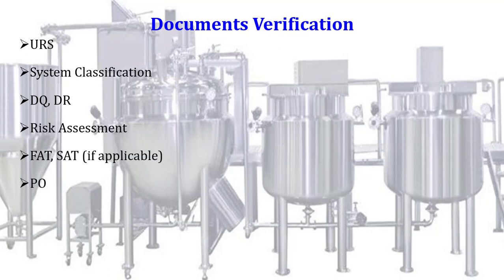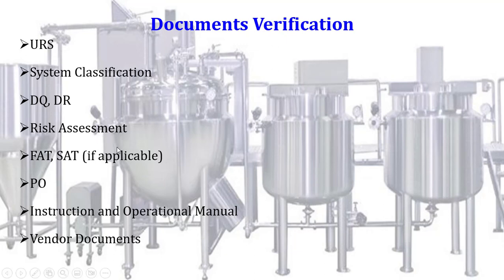In documents verification, we will verify the following documents, which are not limited to: URS verification, system classification documents verification, DQ — design qualification — DR — design reports — verification, risk assessment verification, FAT — factory acceptance test — and SAT — site acceptance test — verification if applicable.